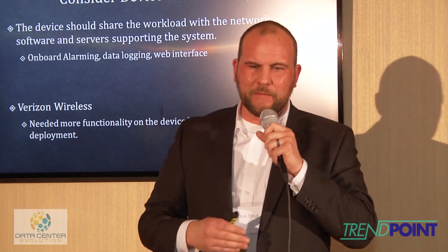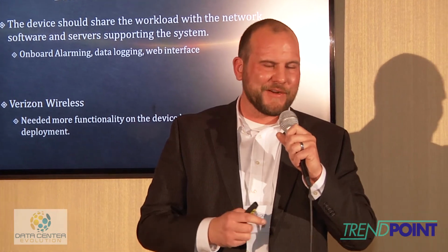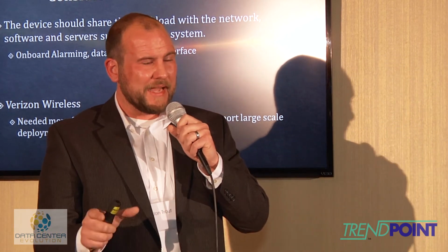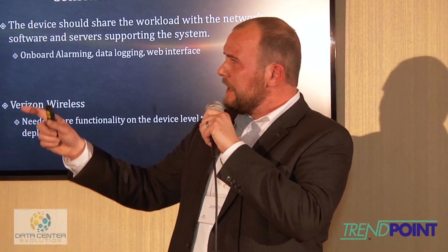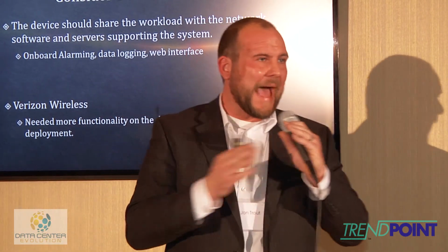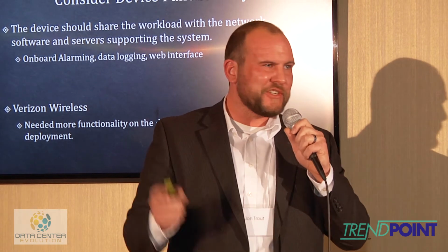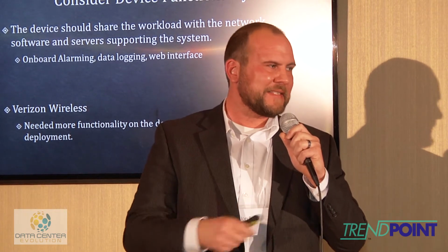And so with legacy devices, they're unintelligent devices. They read data and provide raw data points to the software. So then you have to have a DCIM network, DCIM servers that can handle a polling rate maybe of every 30 seconds, every 60 seconds they get the data. If the communication network goes down, or the server has a problem, not that servers ever have problems, but if the server had a problem, you'd have a gap in your data because the device is just dumb. It's not providing data unless it's asked for.